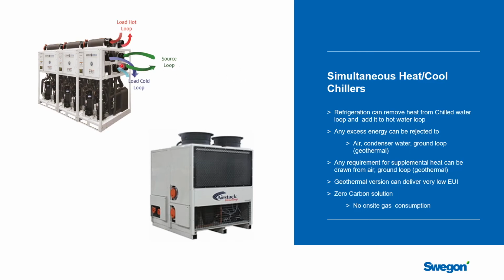This is a water-cooled system, and effectively it has 6 connections. It has a chilled water loop, you can see here. It has a hot water loop, and then it has a source loop. So what this chiller is going to attempt to do is that when there is load both on the heating and on the cooling side, these 2 loops, it will extract the heat out of the chilled water loop. It's going to cool that chilled water back down, and it's going to use that heat to make hot water on this loop.